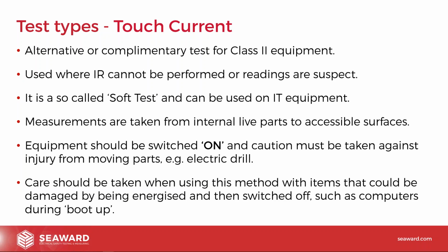So if I was going to touch it, what would I see? Would I see any current? Would I see a low level of current, etc.? So we can use that to test at various points on the equipment and carry out a touch current test to make sure that accessible surfaces are actually safe and that we're not getting any dangerous touch currents present on those surfaces. Again, it's a live test.